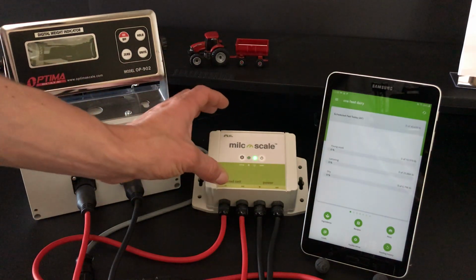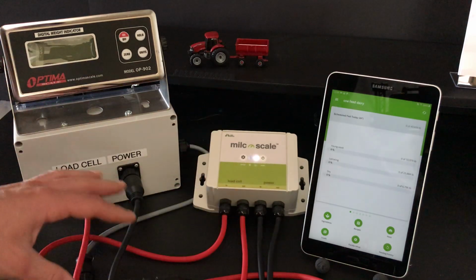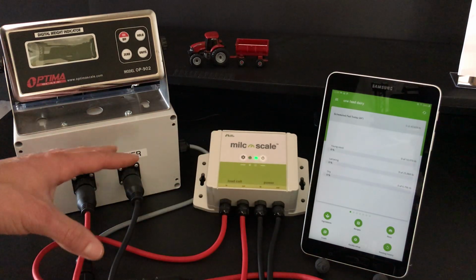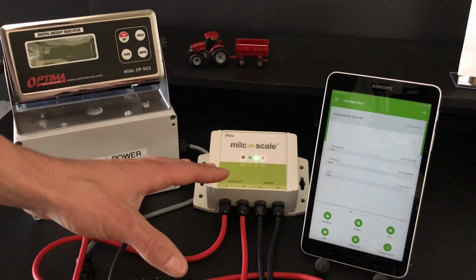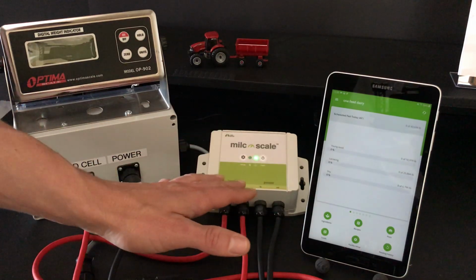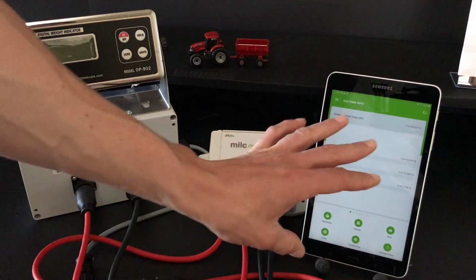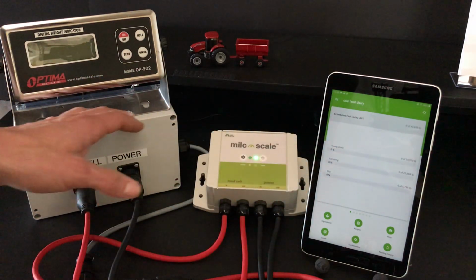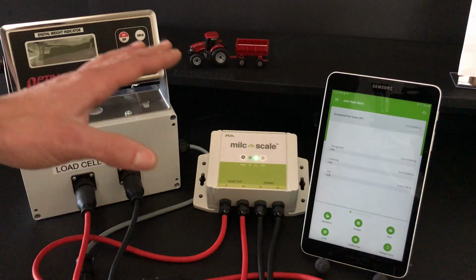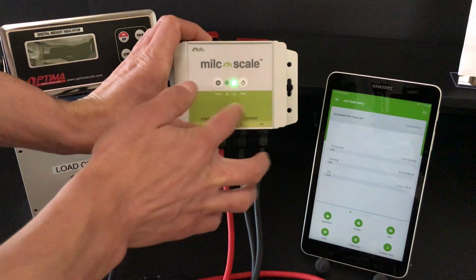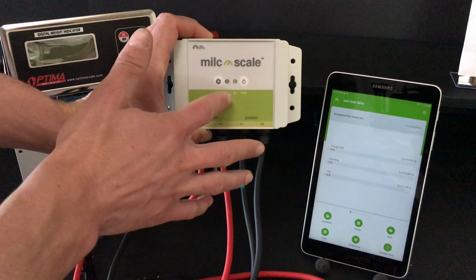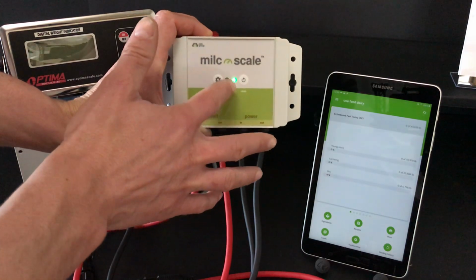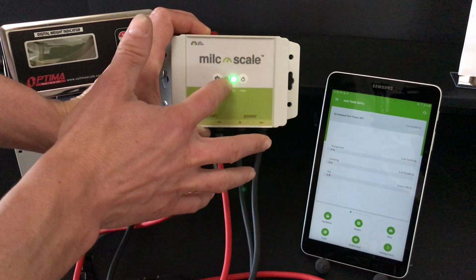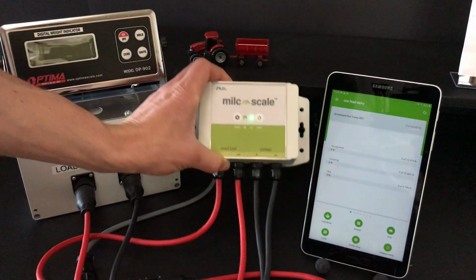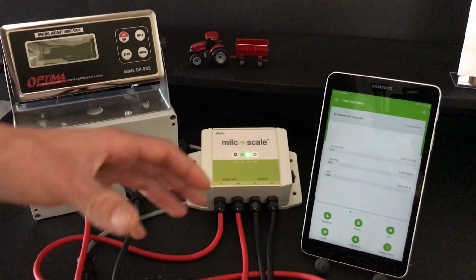Okay, so once we have our milc scale unit properly attached to the scale indicator on our mixer, it's time to do the calibration, which is basically aligning the weights that we see on the app on our mobile device against the weights displayed by the scale indicator. To do that, we first need to point out that we'll see an LED pattern change here when the milc scale unit is not calibrated. It flashes green and flickers pink. And then you'll see how that changes once we have it calibrated.